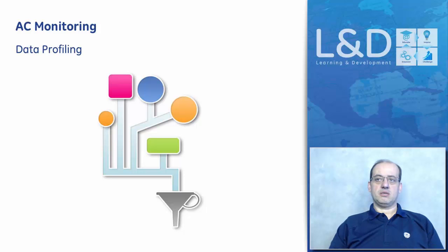The digital data can be any digital input available in your database or from any of your primary equipment. The AC data profiling normally can capture about 100, 200 AC analogs and a couple of digital inputs. The recording and profiling would start with a pre-configured trigger, and once the trigger has stopped, that would stop the recording, and all the data will be profiled inside this COMTRADE file that can be uploaded and viewed for analysis.